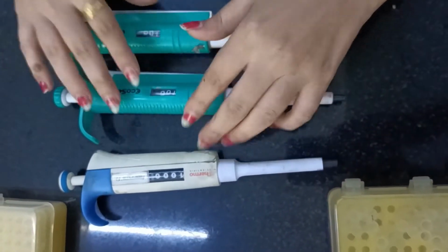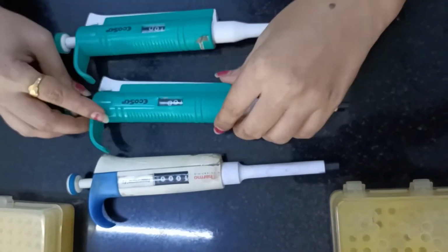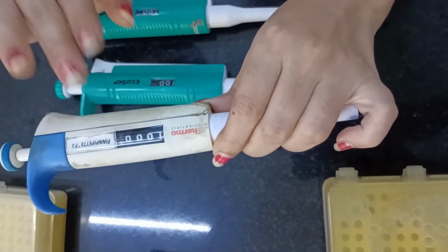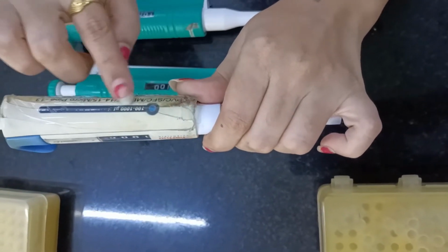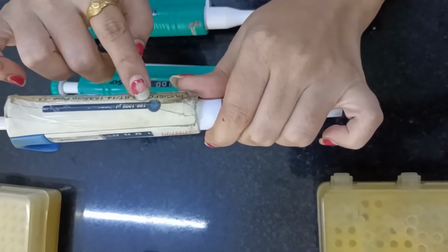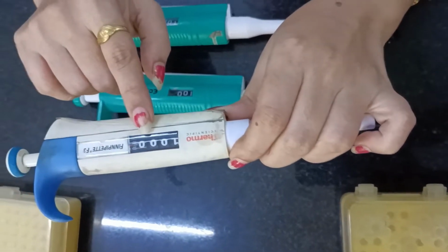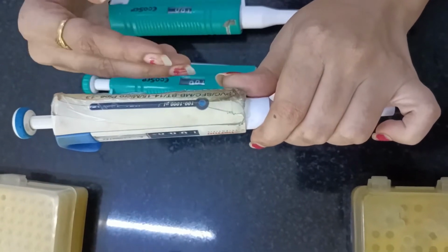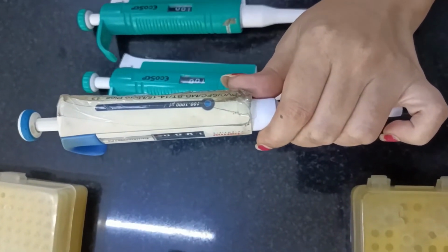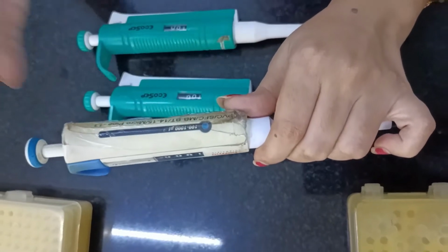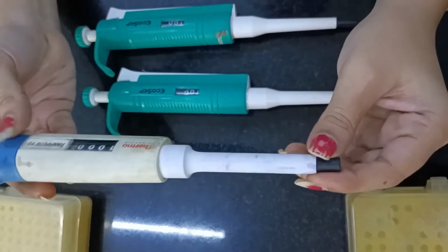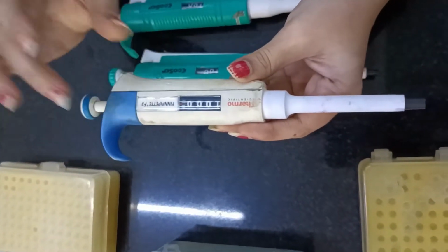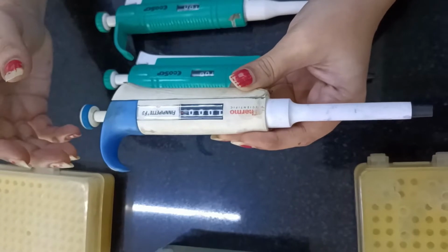Now as you can see over here, let's select this particular micropipette. This micropipette has already been set or has been kept at the higher volume which is mentioned with respect to this particular micropipette, that is 100 to 1000. So it has always been kept at the higher volume over here. If you try to keep it above 1000 microliter, or below 100 microliter, it's going to damage the micropipette.